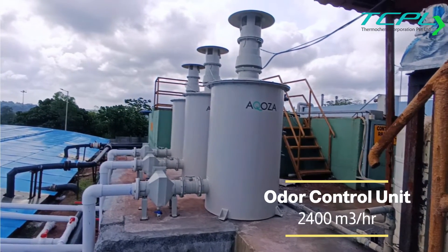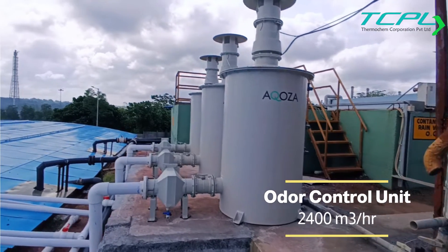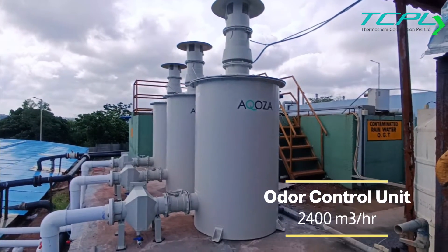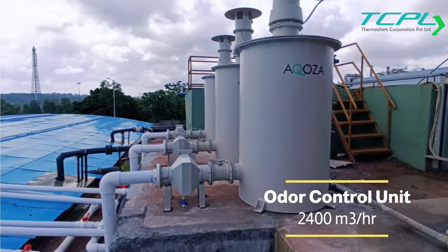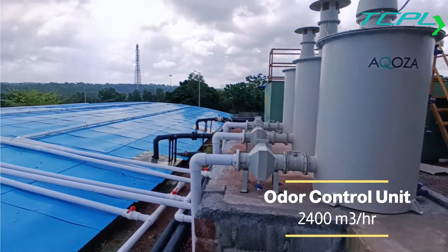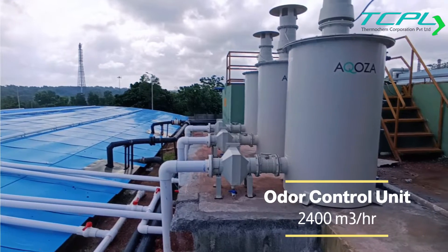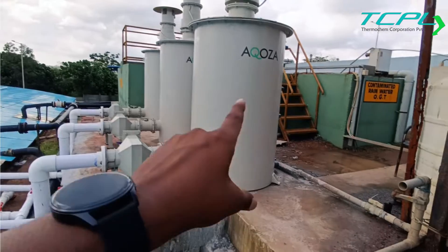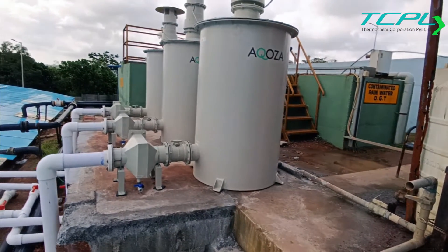The odor control units — the make is AQOZA — and it basically works on an absorption process where the fans are overhead. The total capacity flow is 2400 cubic meters. When the system is switched on, the gases found inside the tanks at the top will be sucked and passed through the pre-filter.